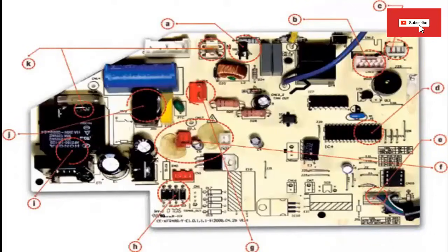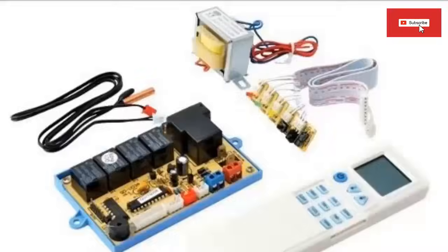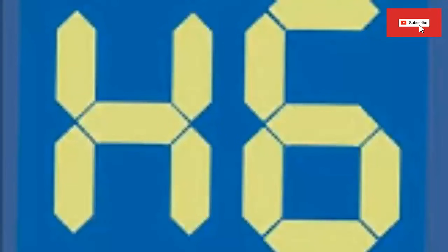The electronic card performs several checks to determine if the fan of an air conditioner is on. Some of the actions the card performs include: 1. Monitor the electrical current flowing to the fan motor, to see if it is receiving power, and the values are normal. 2. It monitors the speed or RPM sensors, to confirm that the fan is spinning at the proper speed. They are mostly Hall effect sensors. These checks allow the card to determine if the fan is on and working properly. Should any of these tests fail, the card may trigger an error code, such as H6, to indicate that the fan is not spinning as expected.